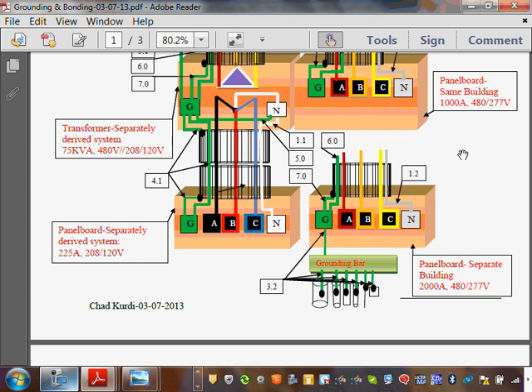Now, I take a 2000 amp from building A to feed a separate structure or building called building B. Now, I'm at building B. Building B is fed from a feeder, not a service, a feeder. When you go to building B, there are a few rules I have to adhere to. Anybody remember the first rule? When you take a feeder to a separate building, you have to have a disconnect for the building.